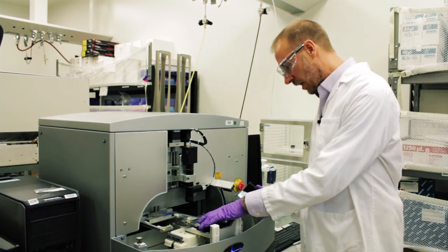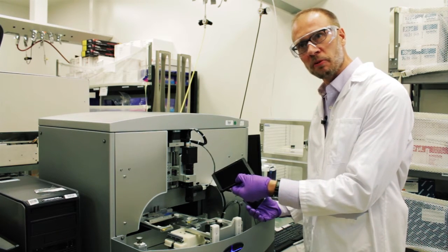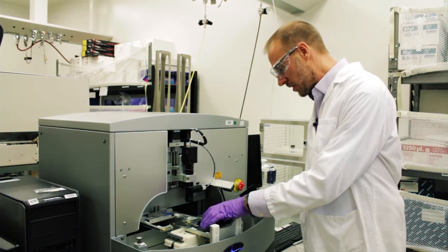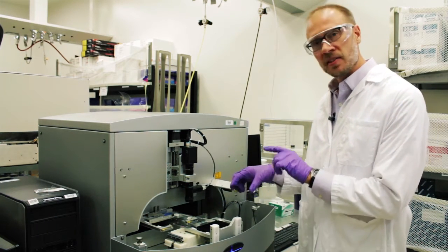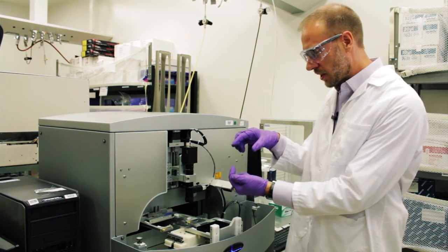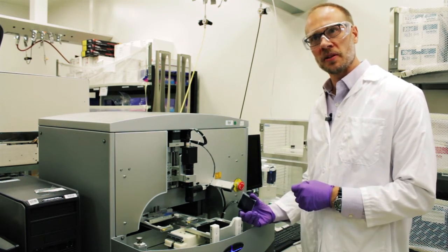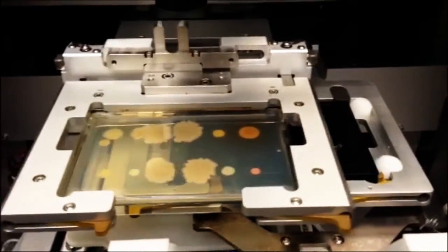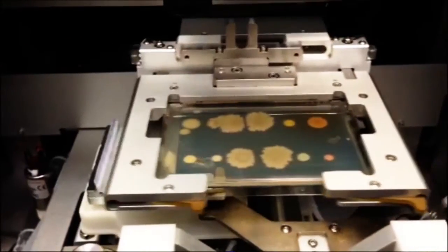The way it works is we have an acoustic plate that we can load our samples in and we can actually perform the enzymatic reactions in this plate. Then we load it in the acoustic printer and it ejects a single nanoliter onto this mass spectrometry surface with very high spatial resolution. It essentially takes our multi-well plate and turns it into an inkjet printer. By doing this we can print an entire plate in only two and a half minutes.